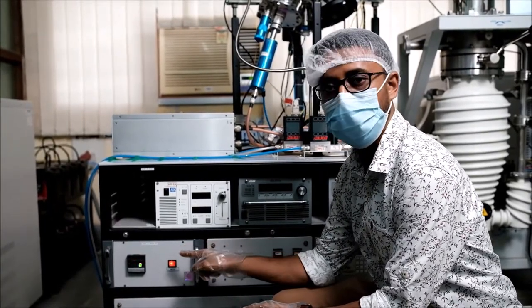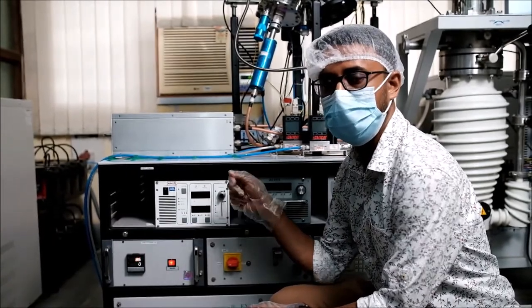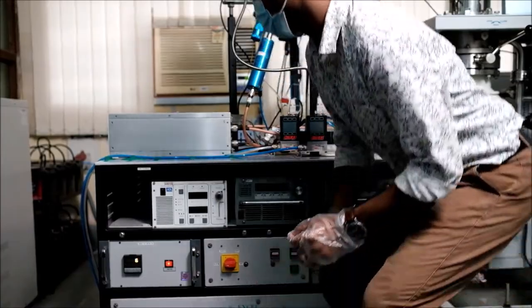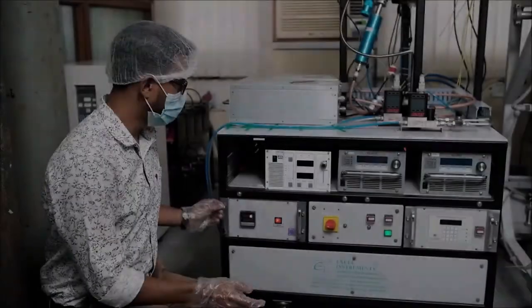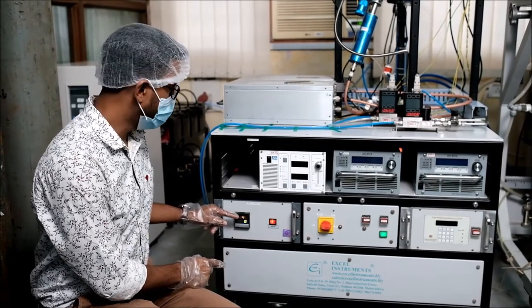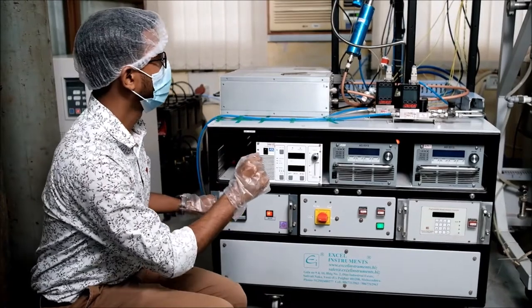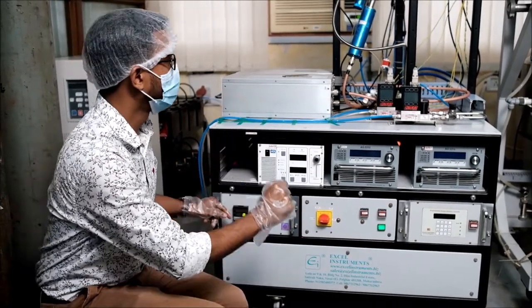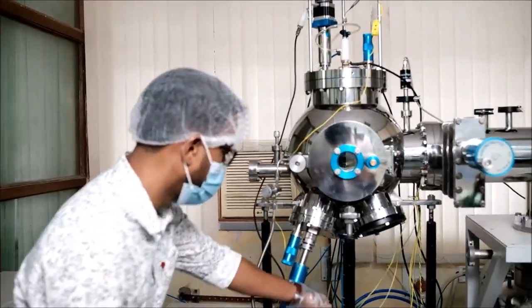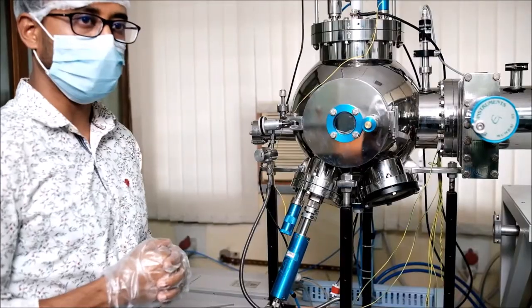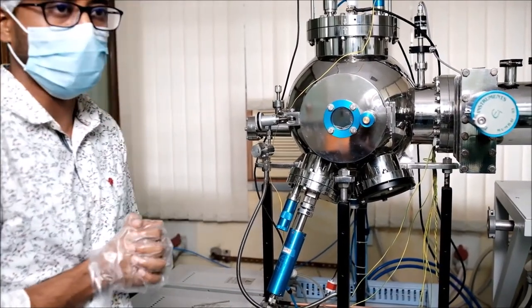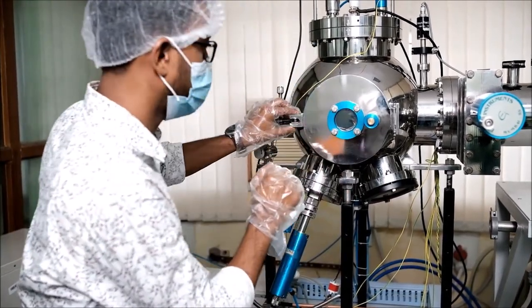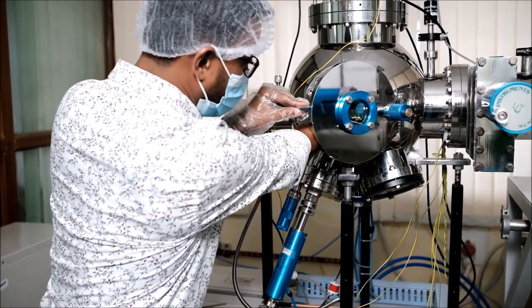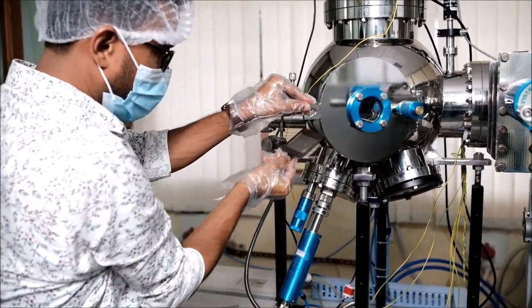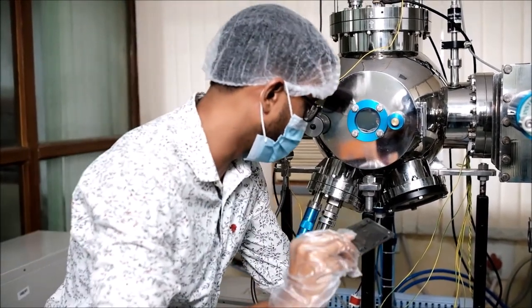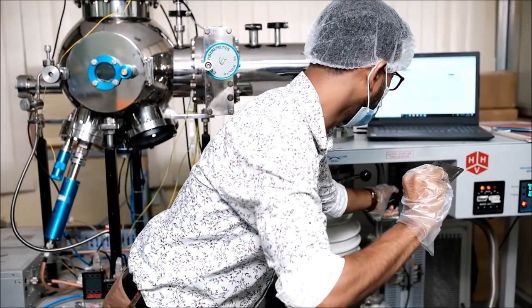Now the temperature is below 100 degrees Celsius, and we are ready to take out our substrate from the chamber. To do that, we will vent the chamber with nitrogen gas. Now the temperature is below 50 degrees Celsius, so we can take out our substrate from the chamber. But before that, we have to vent the chamber to atmospheric pressure. We will do this by the nitrogen gas flow through this ball valve. We wait a few seconds to reach atmospheric pressure, and then we take it out. So now we are ready. I have to take out the substrate. We will close the valve. So we will turn on the roughing valve.